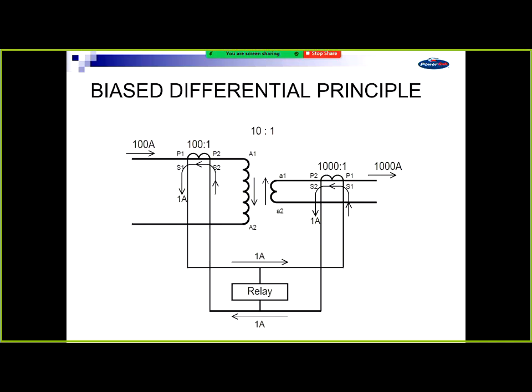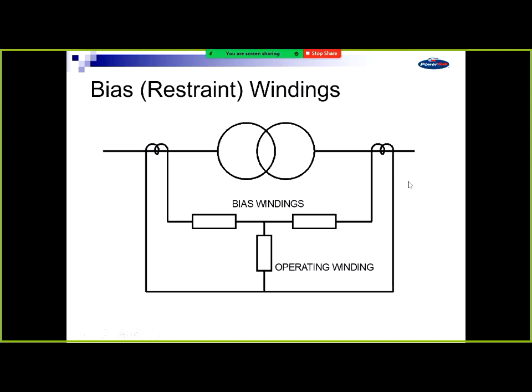This is a simple picture of how, if you had a 10-to-1 transformer, 100 amps on one side, 1,000 amps on the other side, 100-to-1 and 1,000-to-1 CT ratios, you get 1 amp secondary flowing through both CTs in the opposite direction. You get no current flowing through your relay down the bottom there. So that's the simple theory behind it. But we put a bias winding in there, a bias or restraint winding.